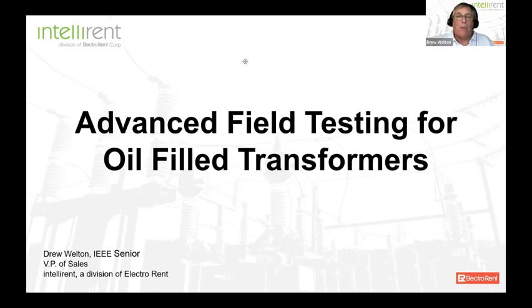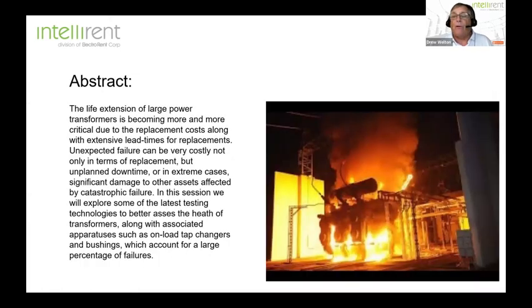And one of the things that I think is very important when we talk about transformers and other very expensive assets in the power system is life extension of critical assets. It is becoming more and more important to us, not only as the price of assets such as transformers and breakers has started to skyrocket, but also because of lead times. To try and source a new transformer these days, I don't know if any of you have had the pleasure of trying to do that, but depending on the size and type of transformer, you could be out 3 to 4 years in ordering a new transformer. So life extension becomes very, very important, and it is something we can control.